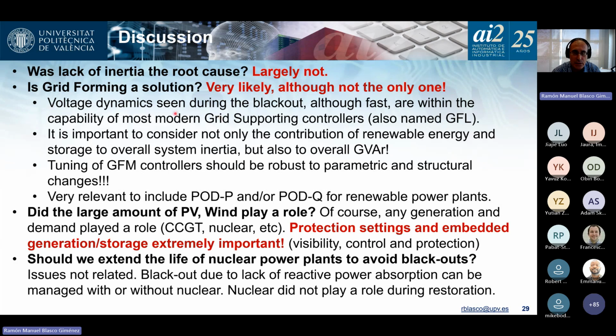The voltage dynamics that you have seen were fast, but we're talking in the range of seconds, not in the range of milliseconds or 1 millisecond. So those could be within the capability of most modern converters. I don't like to call them grid following converters. I call them more grid supporting, because it's not only grid following; they do something more.